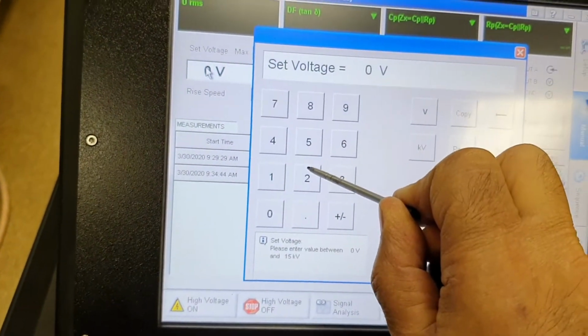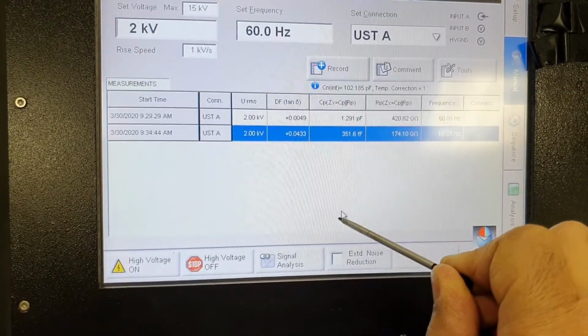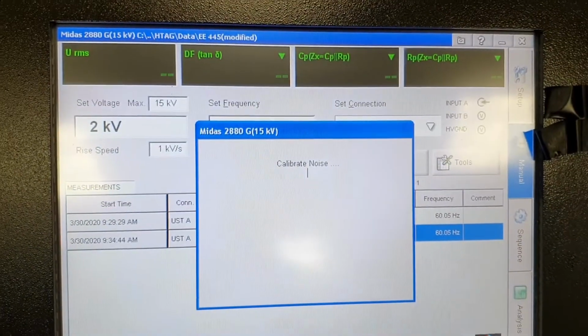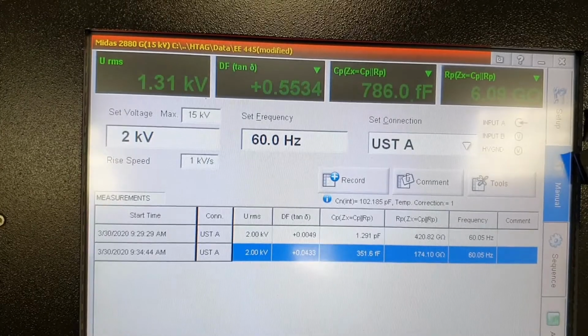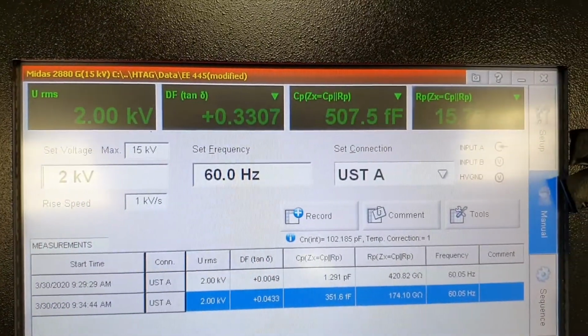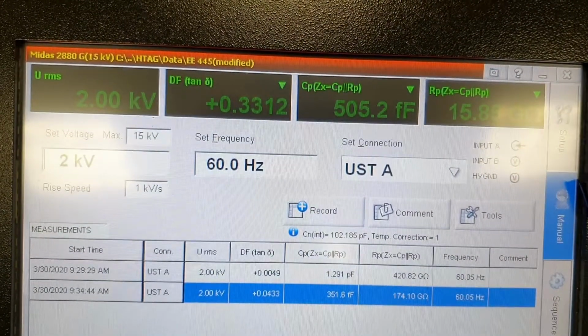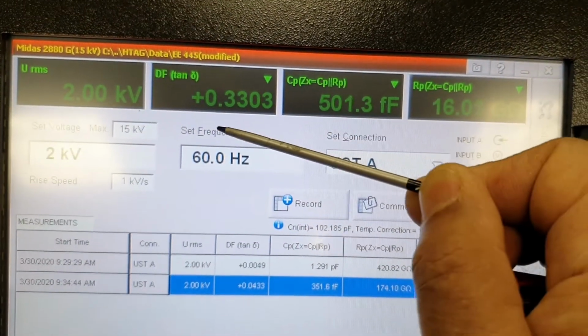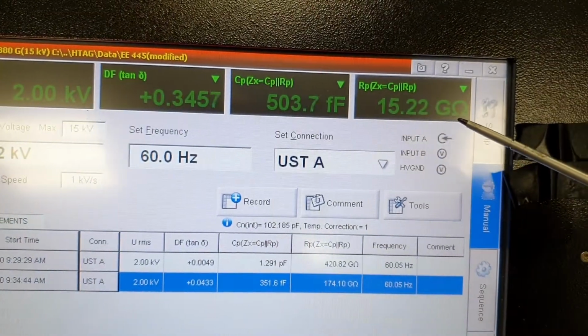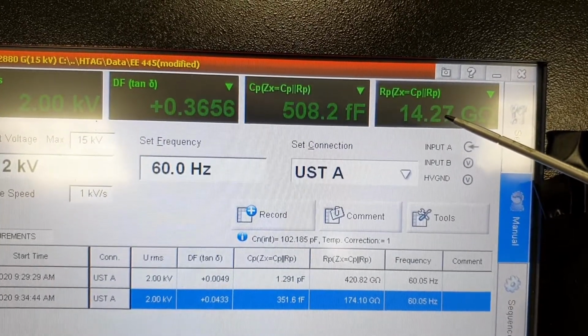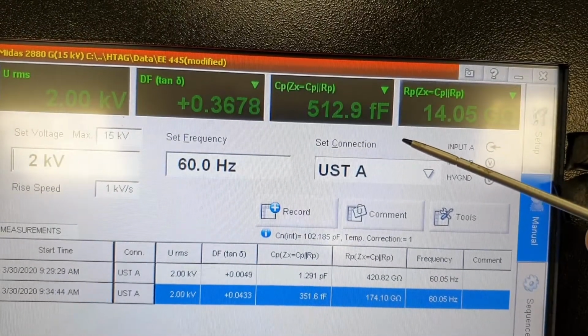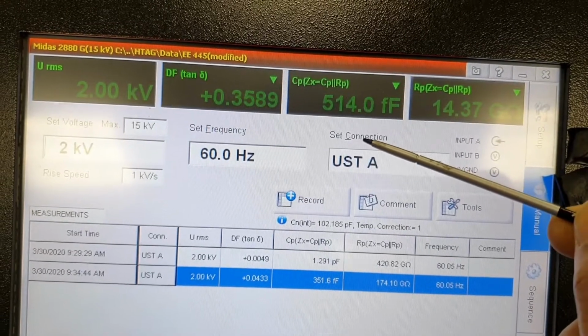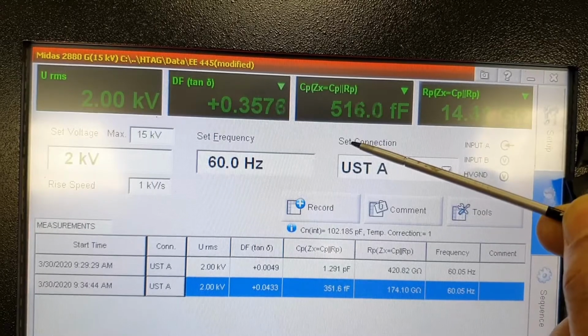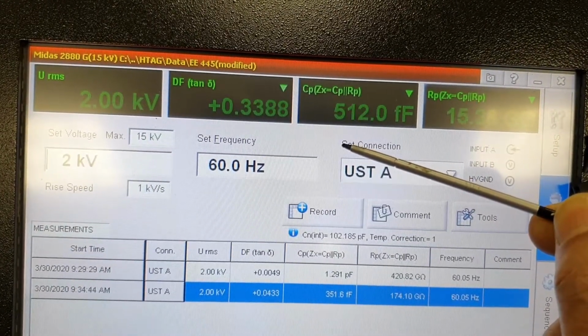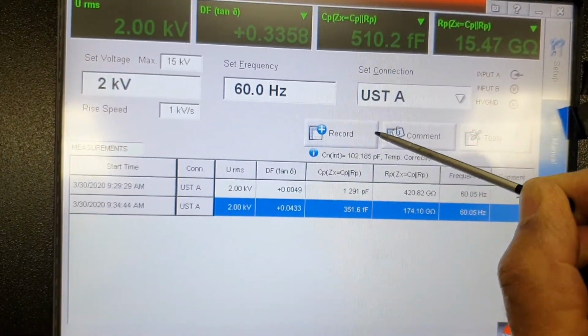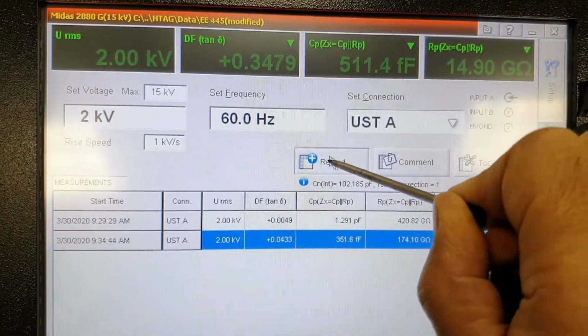So I will again enter the voltage of 2 kilovolt. Okay, press on, then go to on here. So it is again trying to measure the values, trying to adjust itself. Once they stabilize and become very dark green as in the above, you can see the tan delta value has increased from the previous reading. Even the capacitance and resistance have decreased from 174 to 14 giga ohm, sorry. Still taking time.